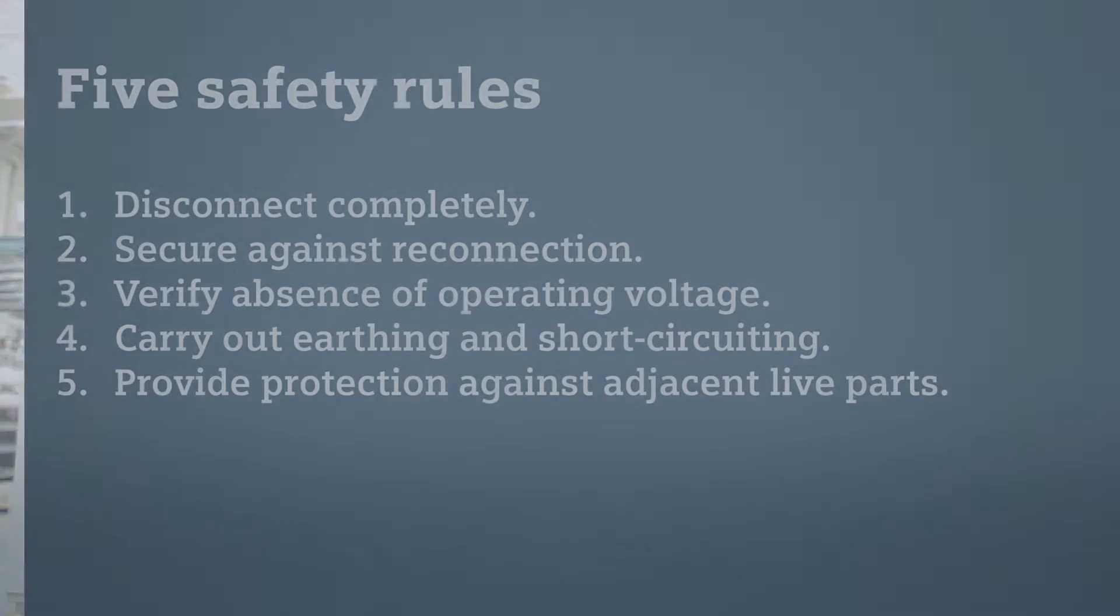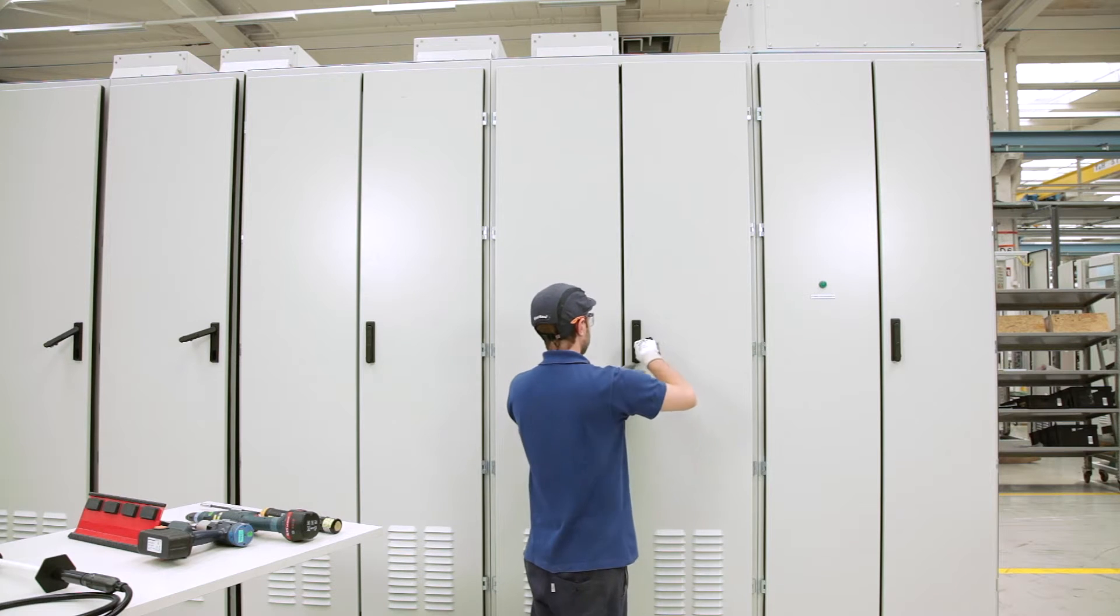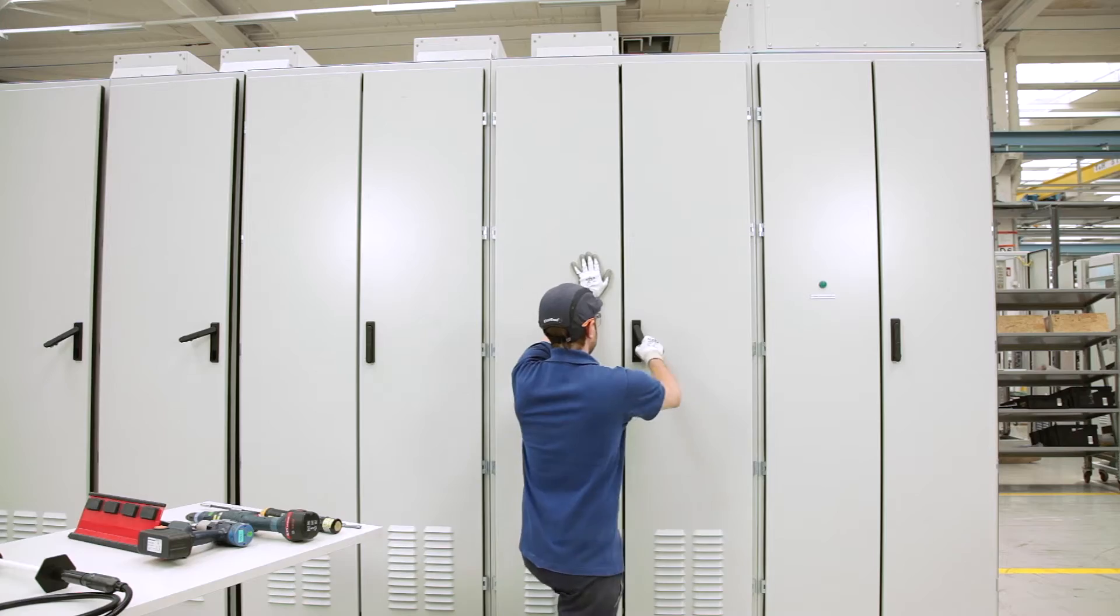In the following video, we will show you the simple steps to prepare the drive for exchanging the cell. After the main circuit breaker has been disconnected and secured against reconnection, open the doors of the power section first before disconnecting also the auxiliary voltage of the drive.